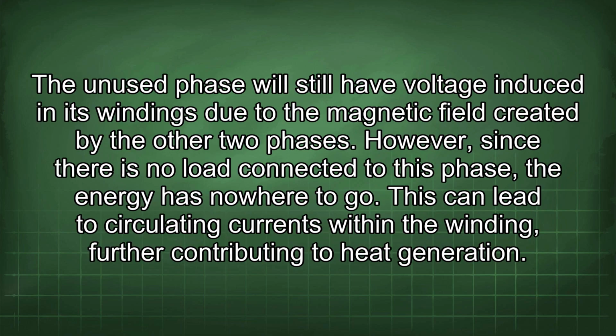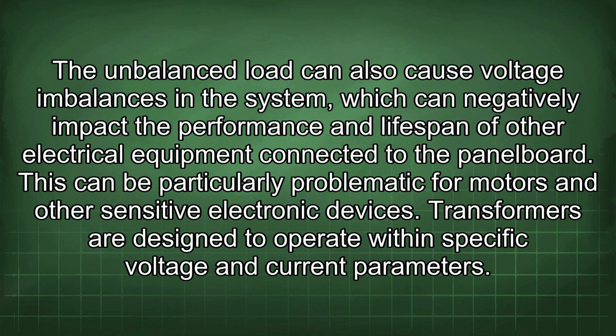The unused phase will still have voltage induced in its windings due to the magnetic field created by the other two phases. However, since there is no load connected to this phase, the energy has nowhere to go. This can lead to circulating currents within the winding, further contributing to heat generation. The unbalanced load can also cause voltage imbalances in the system, which can negatively impact the performance and lifespan of other electrical equipment connected to the panel board. This can be particularly problematic for motors and other sensitive electronic devices.